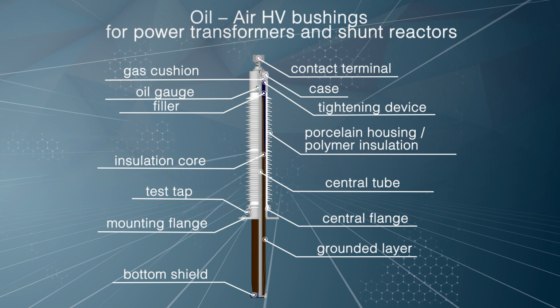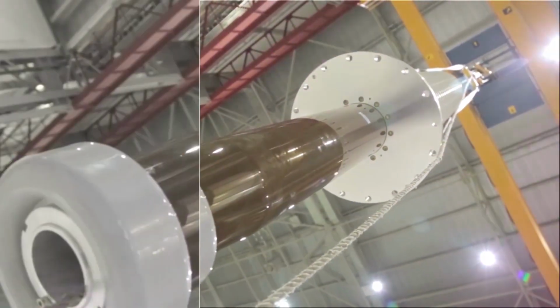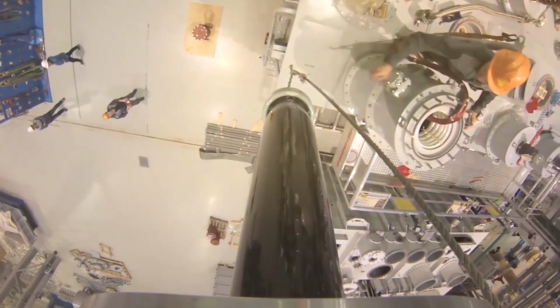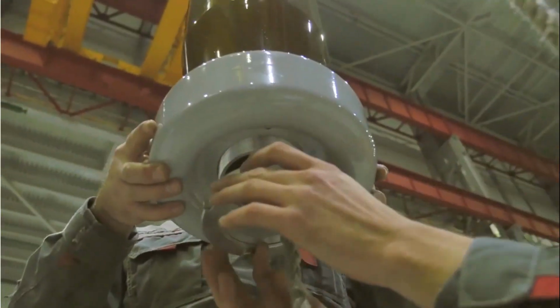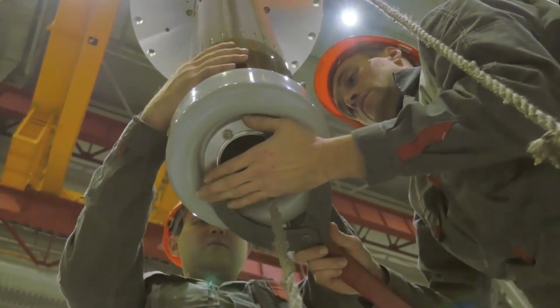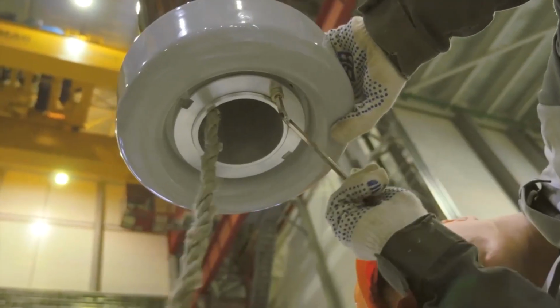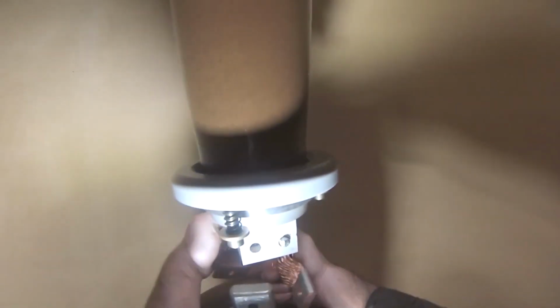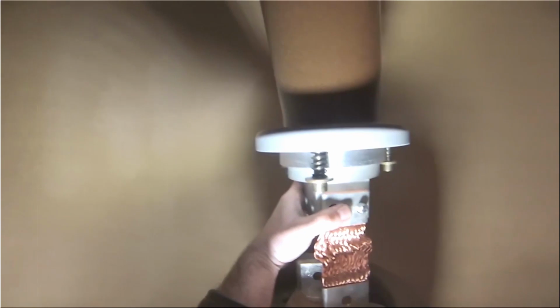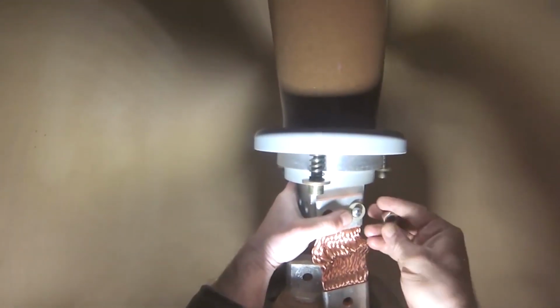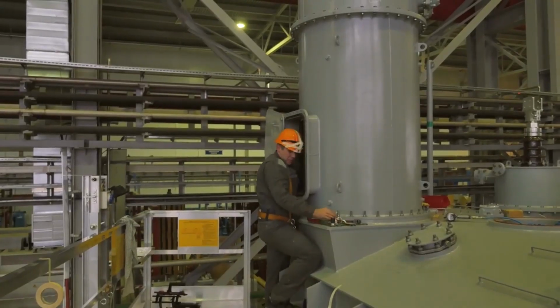functions. Connection to transformer winding can be done in different ways by drawing a cable through the bushing's tube and soldering it to the contact pin in the upper assembly of the bushing, the so-called draw lead type design, by bolting or threaded fastening in the bottom assembly. Then it is not a draw lead type design. In those designs, the central tube or the rod pulled through the tube of the bushing is used as a current conductor.